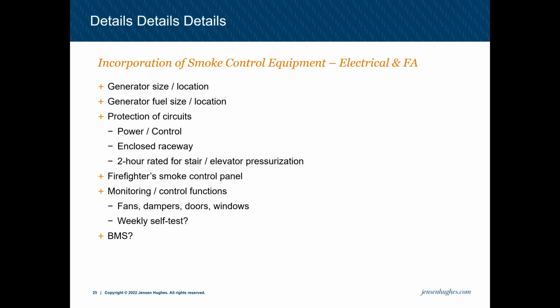Even if it's stair press or elevator press, they're not moving a ton of air. However, these tests usually run for 3 minutes. So in the summer, you'll be putting in 10, 20,000 CFM of outside unconditioned air into each one of your stairs. Similarly, if it's an atrium and you have to run a weekly self-test, atriums are usually the magnitude of 2 to maybe 500,000 CFM of unconditioned exterior air. So having this weekly self-test run in the summer or winter is obviously very detrimental to the HVAC of a building. Similarly, it can create security concerns if you have makeup air doors. If your exterior door is open to the exterior, that creates a big security concern.